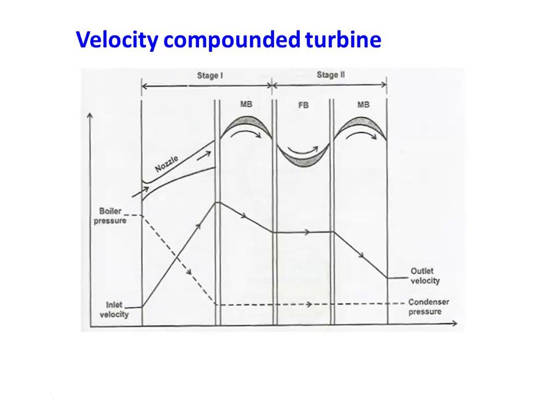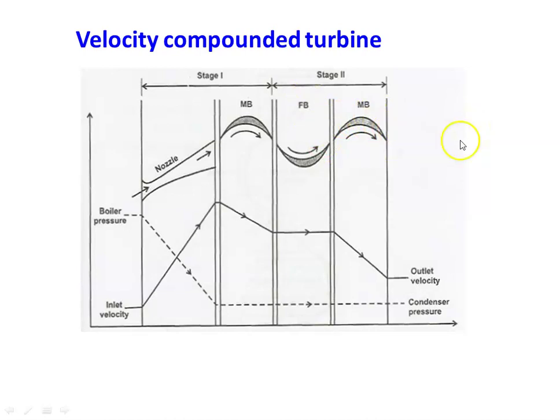First we take the velocity compounded steam turbine, where velocity is used in multiple stages. Looking at the diagram, we have a nozzle at the entrance of the turbine, next a moving blade, then a fixed blade and moving blade. This is a two-stage velocity compounded steam turbine. The first stage consists of a nozzle and a moving blade; the second stage consists of a fixed blade and a moving blade. In the velocity compounded steam turbine, we have only one set of nozzles at the entrance.